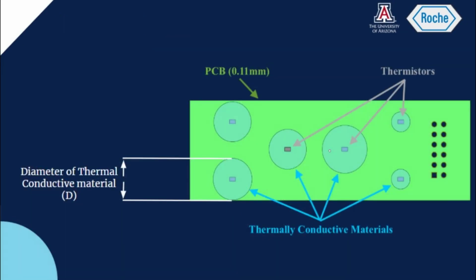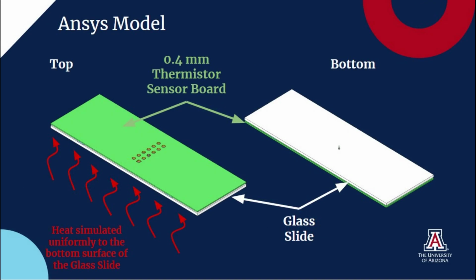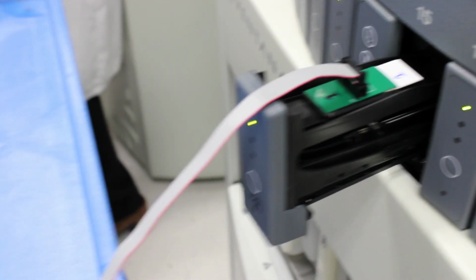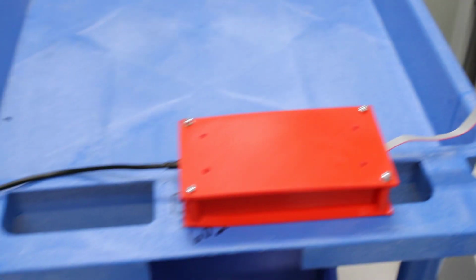Our design uses a printed circuit board with 6 thermistors attached. From the ANSYS modeling, we decided to attach the glass slide to be heated directly to the thermistor board by way of thermal epoxy. This thermistor board is attached to the sensor interface board by a ribbon cable. The interface board is protected from water damage by a 3D printed, sealed encasement. This is where the resistance measurements taken by the thermistors are interpreted into temperatures.